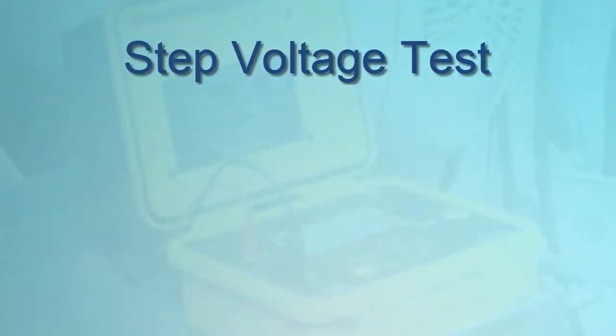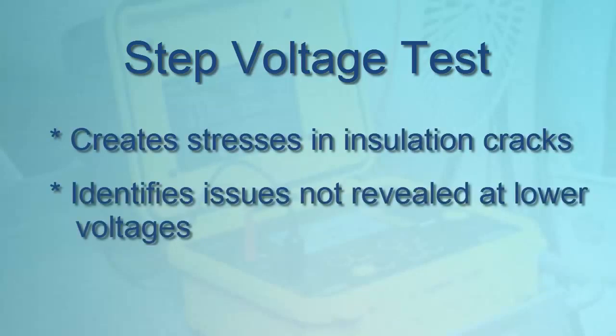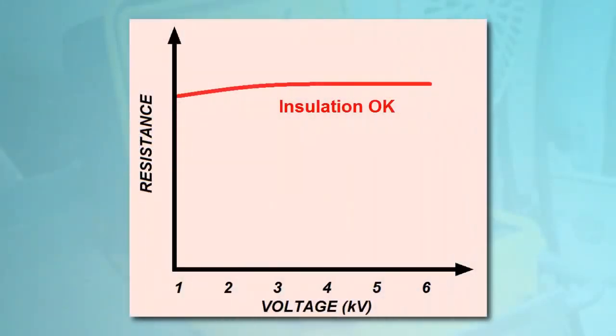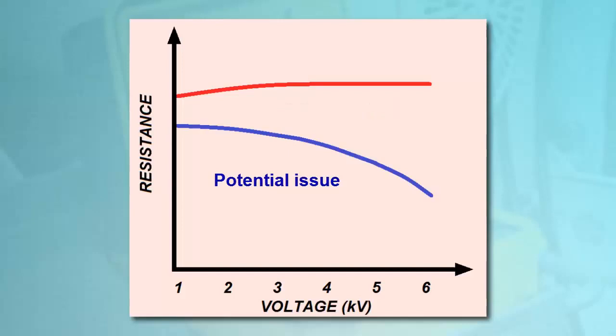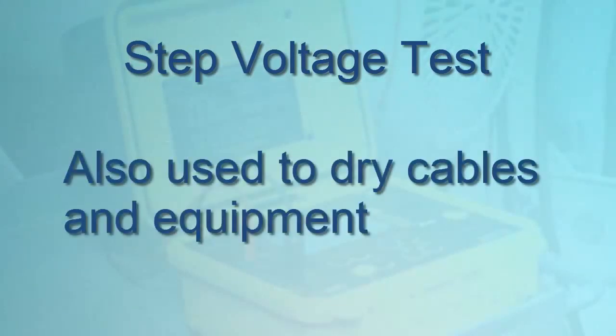The step voltage test is designed to create electrical stresses on internal insulation cracks, identifying potential problems that may not be revealed by testing at lower voltages. Insulation that is thoroughly dry, clean, and in good physical condition should provide roughly the same resistance measurement across the voltage range. If instead you observe a significant decrease in resistance at higher voltages, your insulation may be contaminated or deteriorating. Step voltage testing is also often used as a way to dry wet cables or equipment. Gradual voltage steps, applied for increasingly longer durations, can facilitate drying through heating.